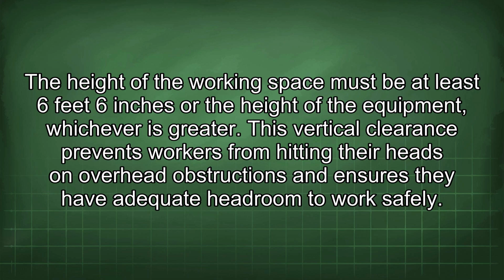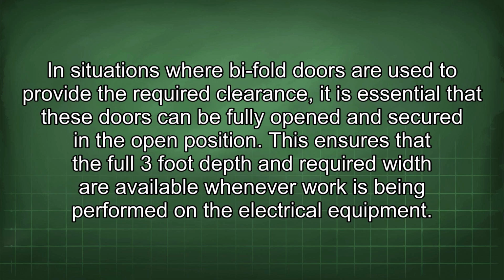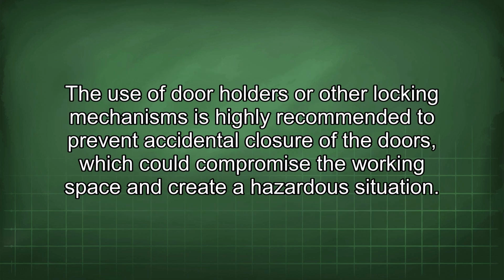In situations where bifold doors are used to provide the required clearance, it is essential that these doors can be fully opened and secured in the open position. This ensures that the full 3-foot depth and required width are available whenever work is being performed on the electrical equipment. The use of door holders or other locking mechanisms is highly recommended to prevent accidental closure of the doors, which could compromise the working space and create a hazardous situation.